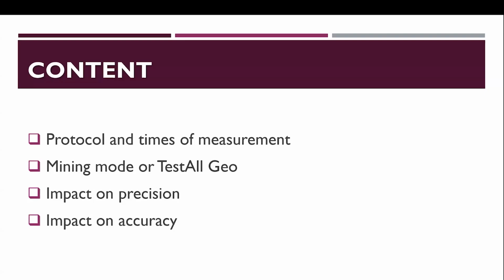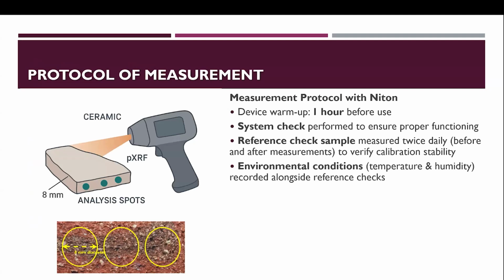Before starting the measurements, the Niton is warmed up for 1 hour and a system check is performed to verify the proper functioning of the device. A reference check sample is then measured twice each day, once before and once after the measurements. This is done to verify the stability of the calibration of the device. The temperature and relative humidity are also measured at the same time as the measurement of the reference sample to ensure the stability of the working environment.